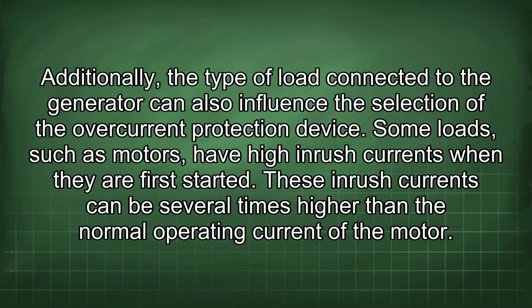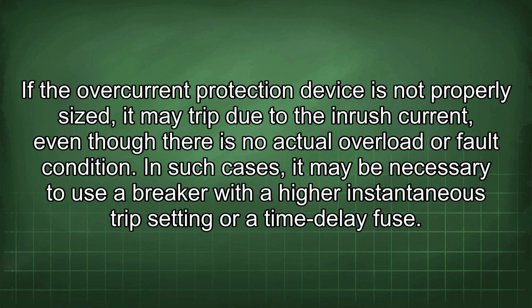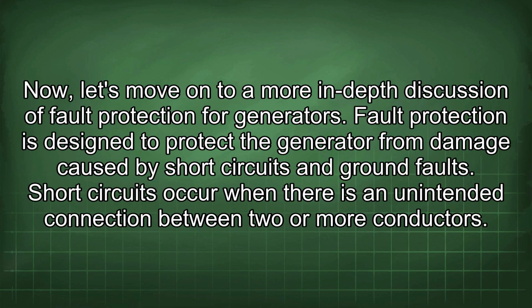Some loads, such as motors, have high inrush currents when they are first started. These inrush currents can be several times higher than the normal operating current of the motor. If the overcurrent protection device is not properly sized, it may trip due to the inrush current, even though there is no actual overload or fault condition. In such cases, it may be necessary to use a breaker with a higher instantaneous trip setting or a time delay fuse. Now let's move on to a more in-depth discussion of fault protection for generators.